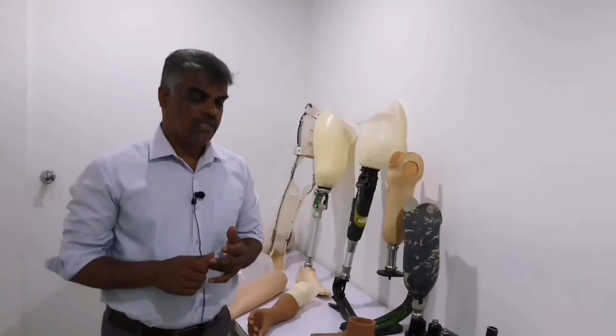In amputee cases, we can see different knee joints like pneumatic, hydraulic, and microprocessor. The pneumatic gives swing control, a very smooth flexion and extension with very little effort. The hydraulic contains oil and is for swing control as well as stance control. Stance control means whenever the amputee is using the limb, it gives stability so it will not buckle. While walking on rough terrain, inclined areas, or stepping down, the hydraulic gives high resistance, so it gives a very good safety mode.